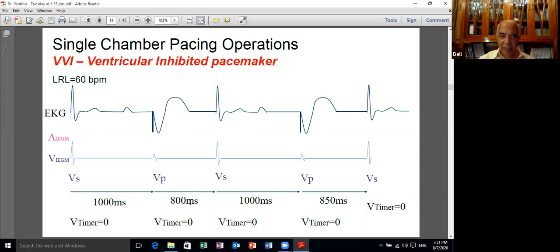But after 800 milliseconds, there is a junctional beat felt by the pacemaker lead in the ventricle, which brings the V timer to 0 and then starts to count 1000 milliseconds. Nothing happened. There is an electrical activity in the atrium, not sensed because there is no lead in the atrium.